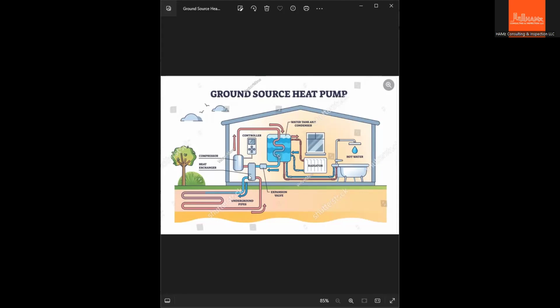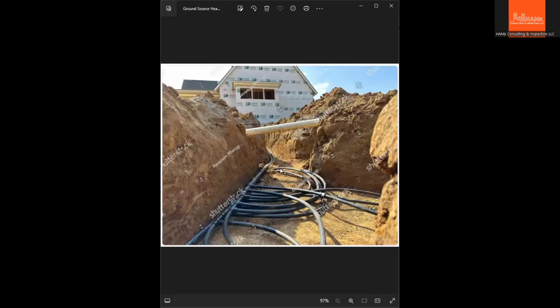This is only one line. The water will travel through the ground, absorbing its heat, to heat up this heat exchanger. So this cold water will go through a coiled type system that has heat transfer between the hot and the cold water temperature. When it comes out of this heat exchanger, the temperature is higher than at the inlet. So this will supply where you have hot and cold water in your shower, in your faucet, and even in your radiators. On the job site, you could see something like this before they backfill the piping in the ground.